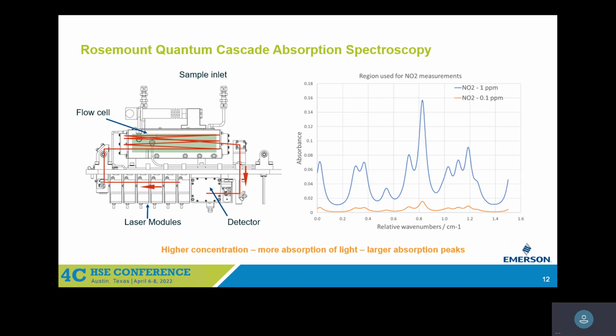The light itself exits to the detector. What the analyzer is actually looking at is the absorption feature of specific analytes. So let's say this laser right here is measuring NO2. At 1 ppm, these are the absorption features that we would see, and at 0.1, you see they're still there, but they're less. Really, in order to determine the concentration, we look at how much light is absorbed, and to understand how much light is absorbed, we look at the area underneath the peak. The larger the area underneath the absorption peak, the higher the concentration.